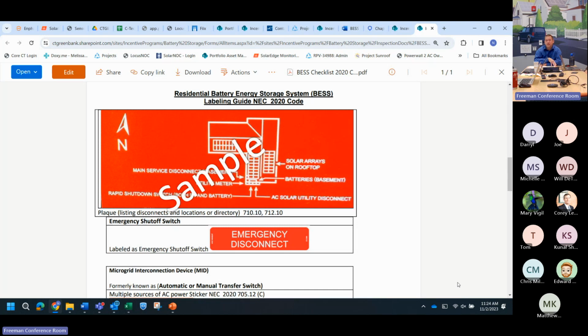The emergency shutoff switch is still nice to have, but in that case it's not necessary. Solar requirements require the open-finger blade disconnect so the utility lineman can open the box and verify the blade is physically open, ensuring solar power can't go back onto the grid while they repair a transformer or downed lines. There's no such requirement for batteries that I know of, which I find strange—maybe utility companies are a bit behind the times. You still need a disconnect outside that can shut off the batteries, which is code, but it doesn't have to be the open-finger blade the utilities require.